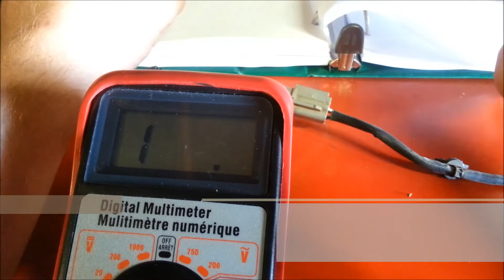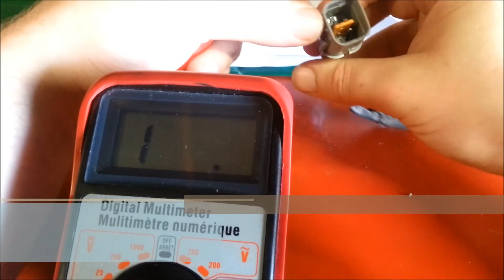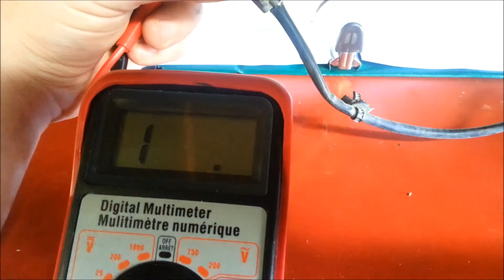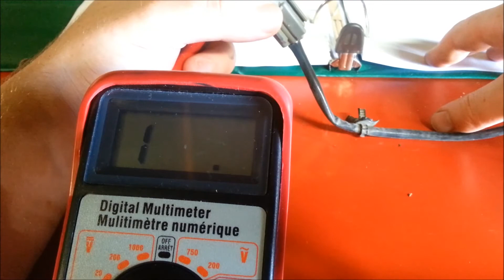Since this should only produce resistance on the heater, we check 3 and 4. Now, it says measure the resistance between 3 and 4, but in the actual picture layout, 3 and 4 would be main relay and heater control, not sensor ground. So 3 and 4 should be the bottom two — I'd say this is it.